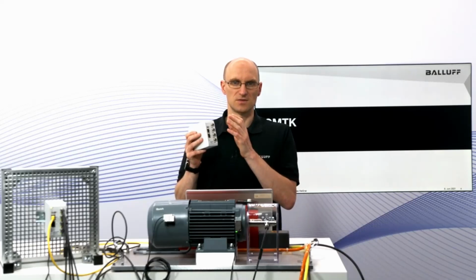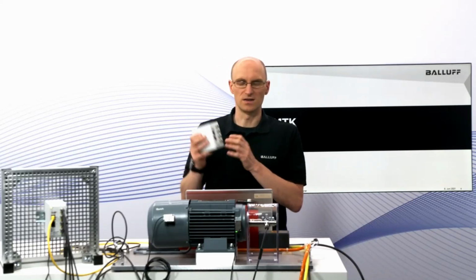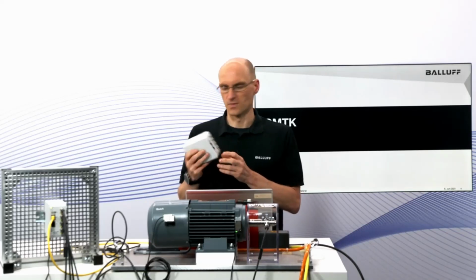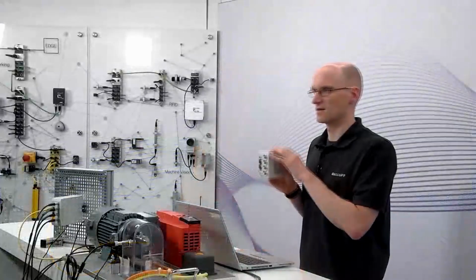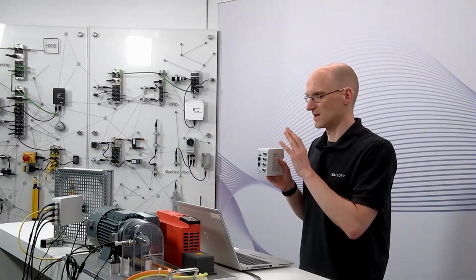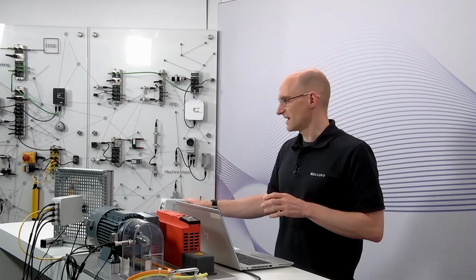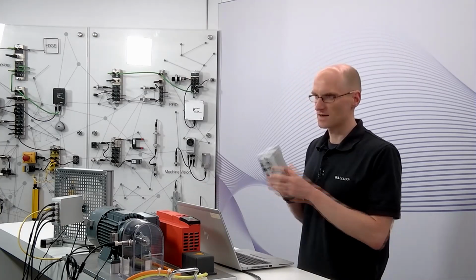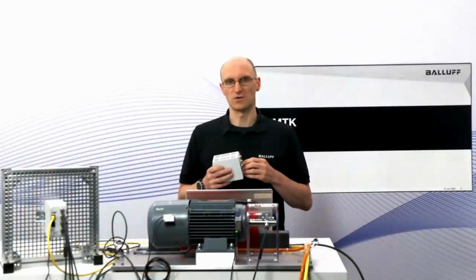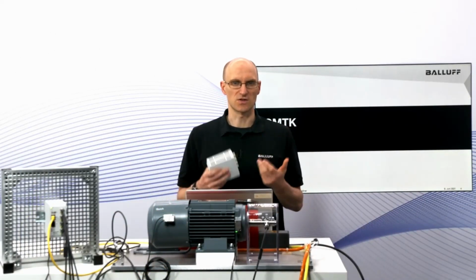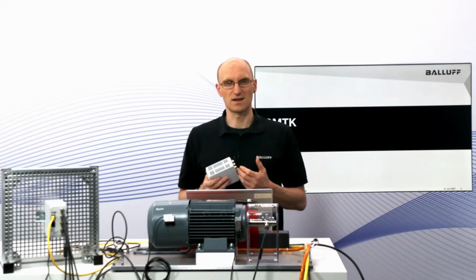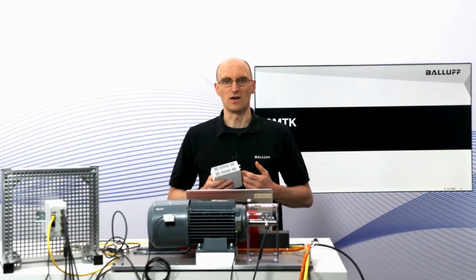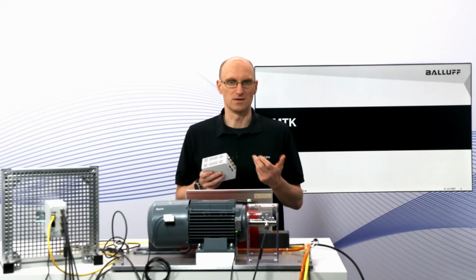So you can connect to the system directly either via LAN, or you can integrate it into your local IT network. In addition, if you just want to do data collection, you can also run it completely independent of a connection. Data will be stored on the device. The second component of the Condition Monitoring Toolkit is the software. This software runs directly on the device and makes it very easy for you to set up the system. So it just walks you through the steps, even for any arbitrary sensor, then to collect the data, to analyze the data, and even send alarms with thresholds that you set.